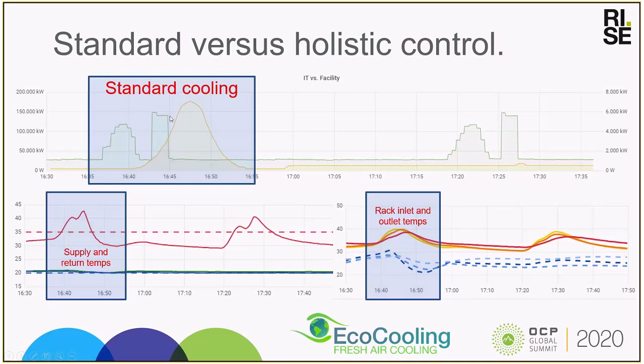it starts to challenge the hot aisle temperature, I guess, and then there's a lag. This is the important thing, a big lag, because the coolers are responding to the increased temperature, which has come and gone in a sense, all the workload's come and gone, but the temperature has been read just at that point. So you can see the supply and return temperatures here for the cooling, the eco coolers, and you can see the rack inlet and outlet temperatures here.